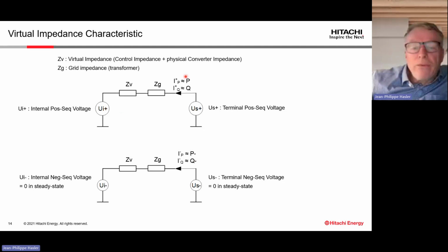Also, I would like to define the quantities we are observing when we are talking about grid forming. In fact, it is power and reactive power. Power means only the power due to the positive sequence of the current, the same as for the reactive power. This is more or less equivalent to what we call the active power current, which is the current component causing the power at nominal voltage. It's the same for the reactive power.